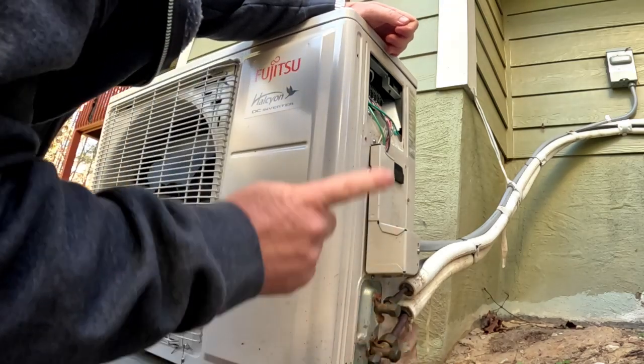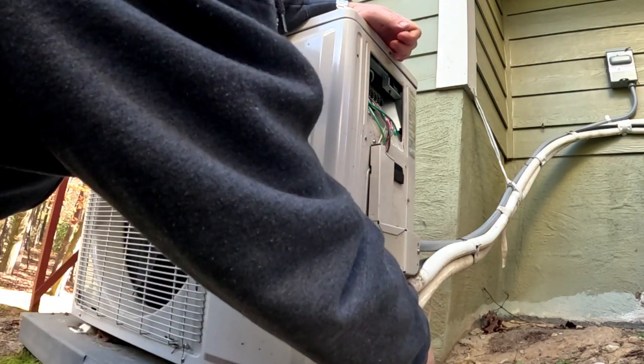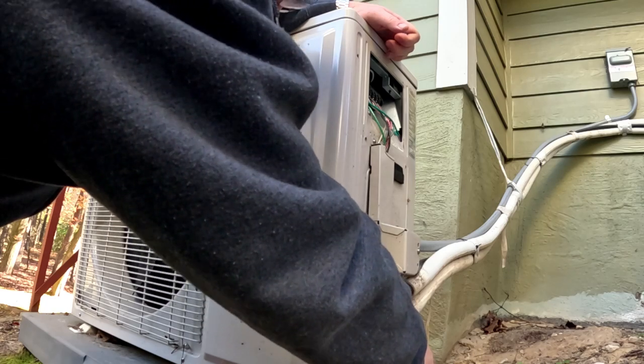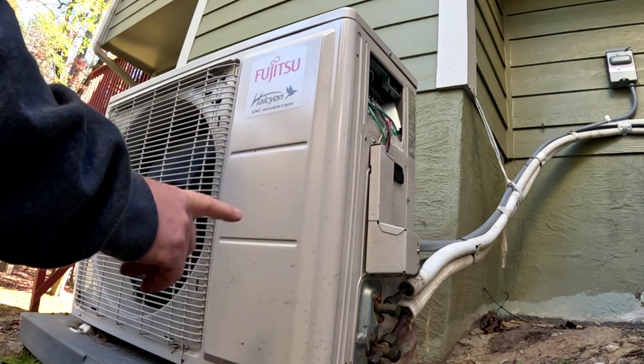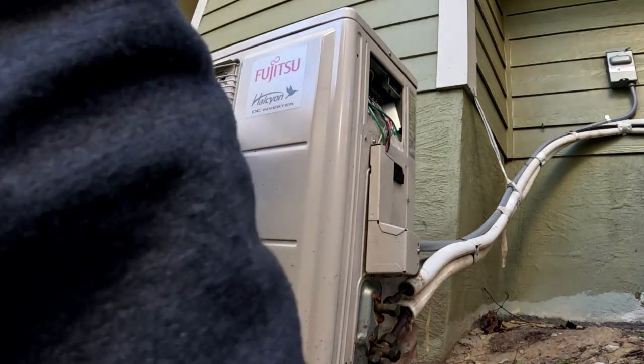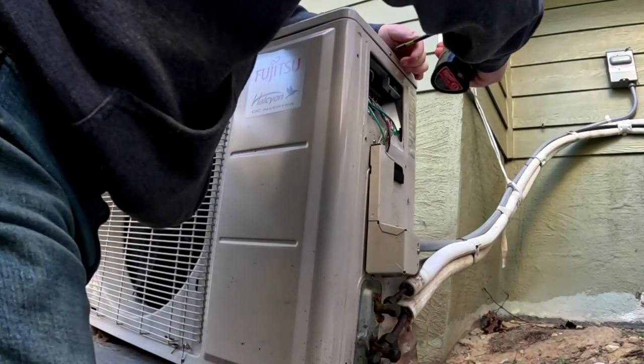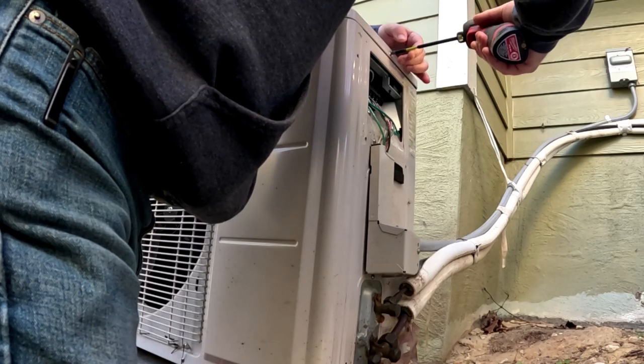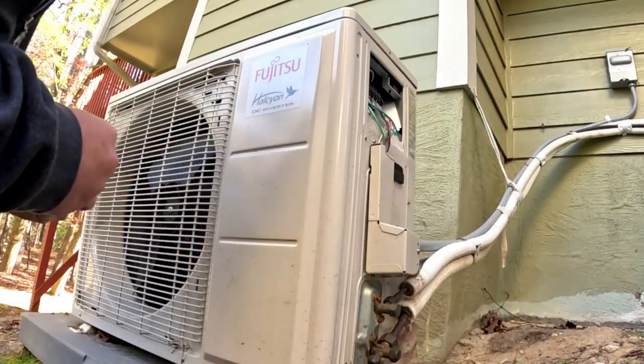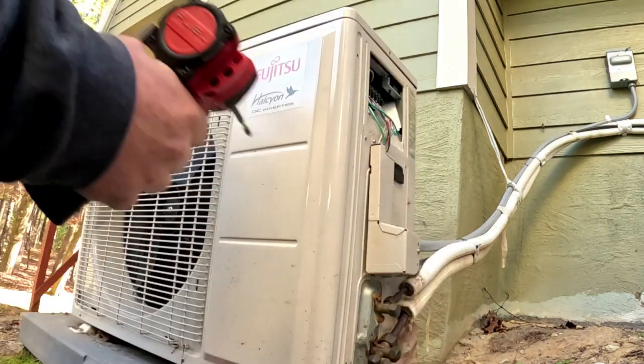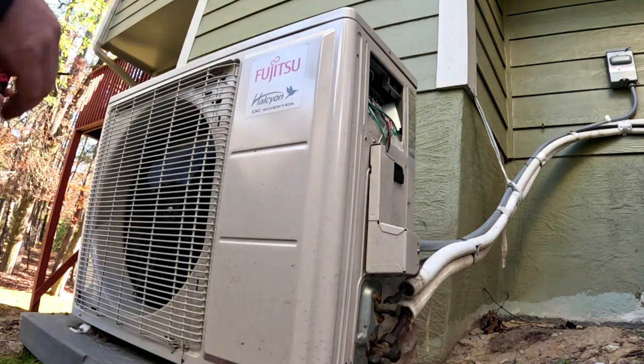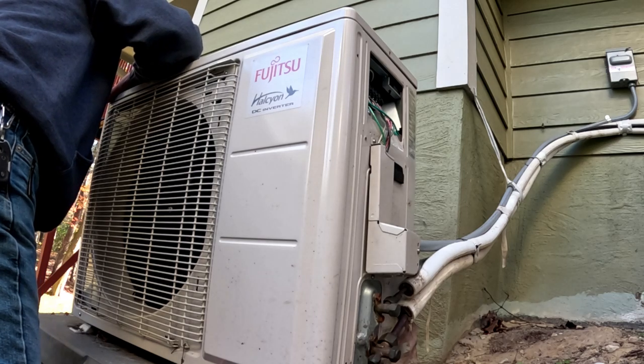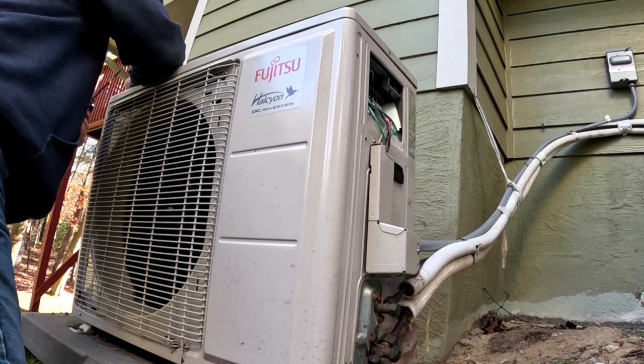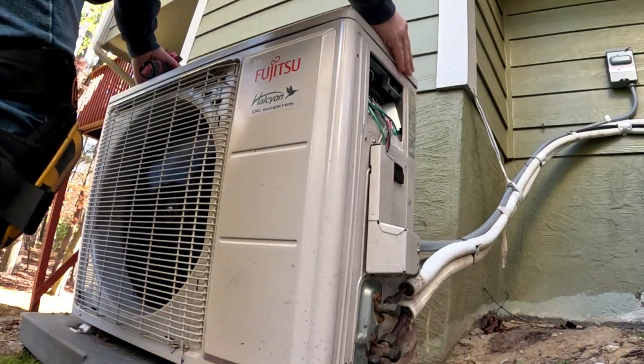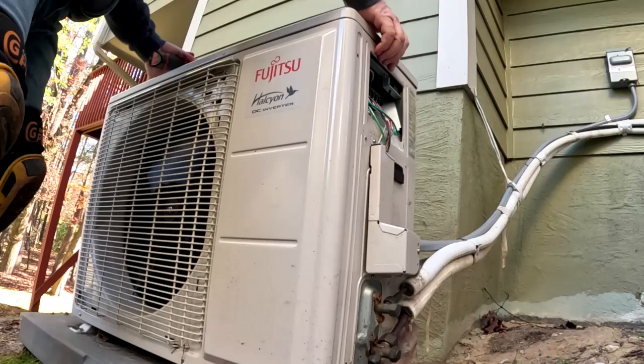any oil. Now I did turn it on in heat when I was up there, and then it went into that lockout. It's cold on that pipe, which tells me it was running in cooling for that little bit of time that it was on. So evidently, maybe it has a sensor in the indoor unit, possibly on the coil, or sometimes they call it the heat exchanger sensor or whatever. And if it's not getting warm when it's in heat mode, it'll shut this thing down. Maybe it interprets it as running in cooling, and that's why it does that. I don't know.